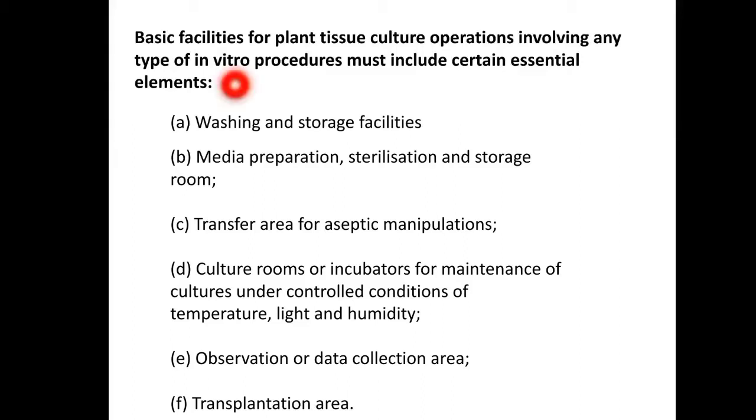The next one is the media preparation room, sterilization room, and the storage room. The media preparation room should have sufficient space for the chemicals, labwares, and the equipment required for weighing and mixing: hot plate, pH meter, water bath, burners with gas supply, microwave ovens, autoclaves, etc. Space is also required for the storage of the prepared media.